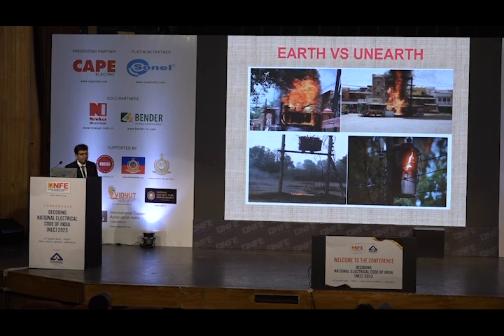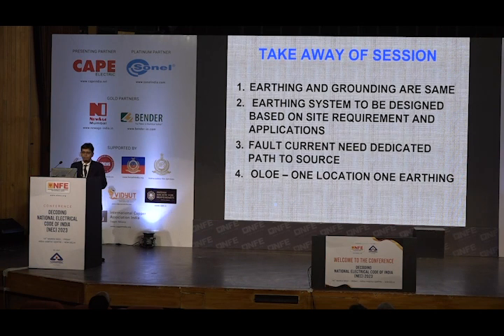In the absence of earth, the system becomes unearthed, and unearthed itself is a disaster. We have to avoid it. Now, time to talk about the takeaways of this session. Earthing and grounding are the same. The earthing system is to be designed based on the site requirements and applications. Fault current needs a dedicated path to the source. Last but not the least, a very important point, OLOE should be the mantra. One location, one earthing. One earthing system for one location is the takeaway.